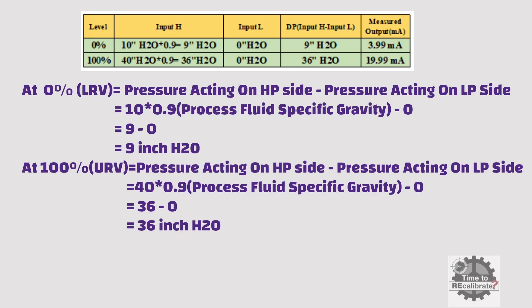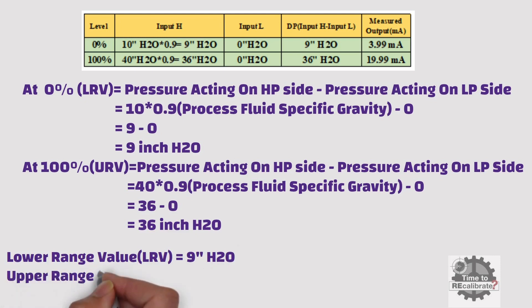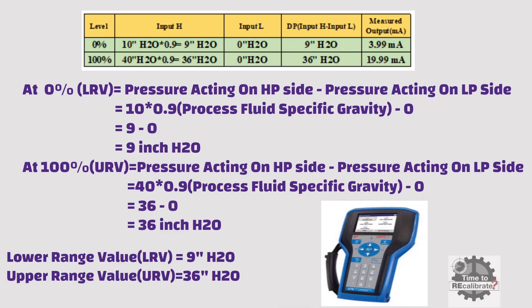Now let's understand the calculation for 100% level. At 100% level, the pressure acting on the high port side is 40 inch H2O, and it is multiplied by the specific gravity of the process fluid, which is 0.9, giving 36 inch H2O. The DP transmitter low side has 0 inch H2O pressure, so the differential pressure is 36 inch H2O at 100% level. In this example, the lower range value is 9 inch H2O and the upper range value is 36 inch H2O. We need to set 9 inch H2O as the lower range value and 36 inch H2O as the upper range value in the DP transmitter using a HART calibrator. In conclusion, level measurement in a closed tank with a dry impulse line always gives a positive calibration range for the DP transmitter.